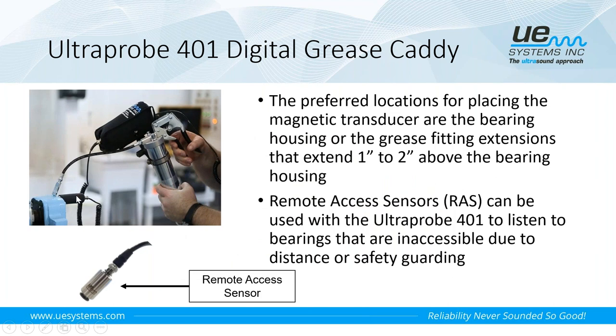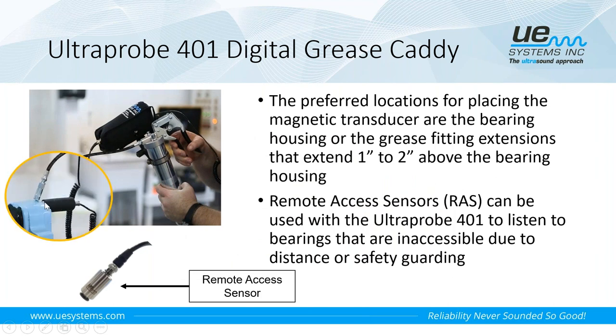Again, the preferred location is going to be the closest point to the bearing or the bearing housing here. And even better is if you have the grease fitting extensions that extend up just 1 inch to 2 inches above the bearing housing, you can take that magnet and just pop it right on the side of that grease fitting. The thing that we like about that is we're testing in the same location every single time. So we're using that grease fitting as our contact point, and that grease fitting extension acts like an extension of the contact probe, if you will. So that sound travels pretty well via that contact probe.